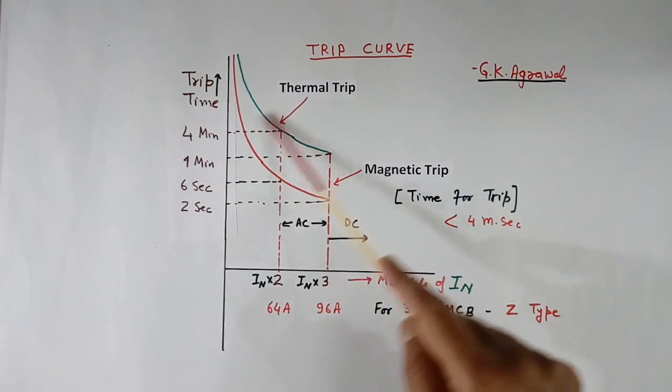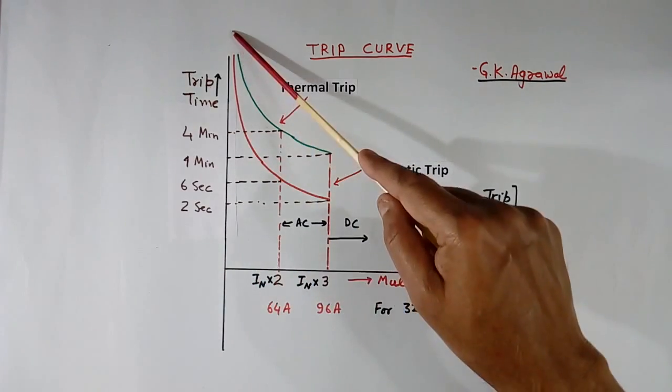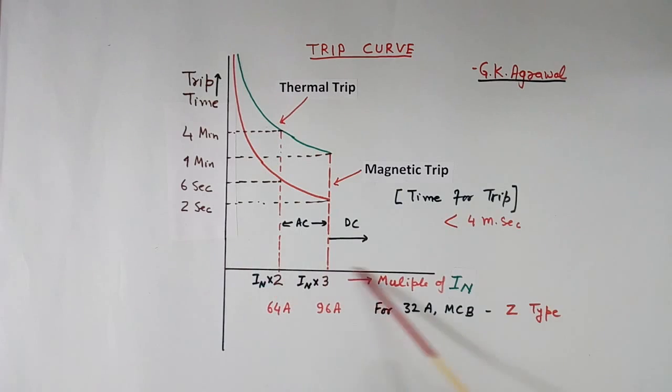This is the trip curve of MCB. This is trip time, this is trip current. Both will be in log scale. This current is written in multiple of IN. IN is nominal current. For example, 2 means IN×2. Suppose IN is 32 ampere for 1 MCB, then this will be 64 ampere, double of this. Similarly 3 means 3 times of this, 96 ampere.